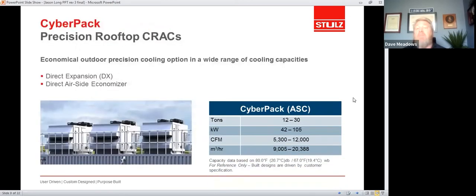I definitely want to spend some time talking about the Cyberpack product, because I think this is a product that we see a growing demand for, for many reasons. The Cyberpack is a true rooftop CRAC unit. And that means that it's designed for some very specific things: tight controls, high sensible heat loads, very high return air temperatures. There are some great advantages to this type of CRAC. What it does is it moves the cooling infrastructure away from the white space, so that white space can be maximized for revenue generation, as opposed to being the location for the cooling equipment for the data center.